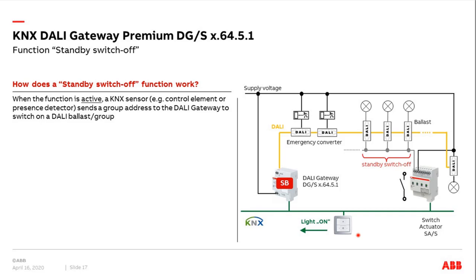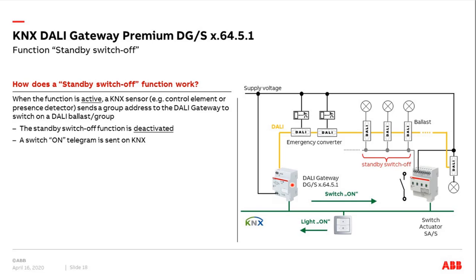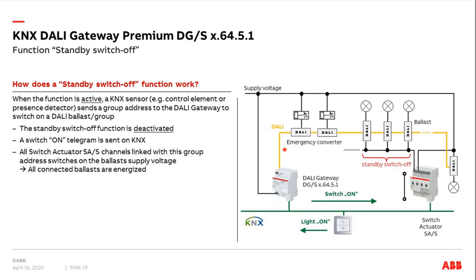Next day or next morning, we enter the building, the presence detector or someone presses the control element. We send a telegram to switch on lights — for example, group number 5 or ballast number 20. What happens first: the standby function is deactivated and the DALI gateway sends a KNX telegram with the logical value one. The switch actuator closes the relay and all the ballasts are now energized. After a delay time set in the gateway — typically one second, maximum up to ten seconds — all ballasts are ready for operation.